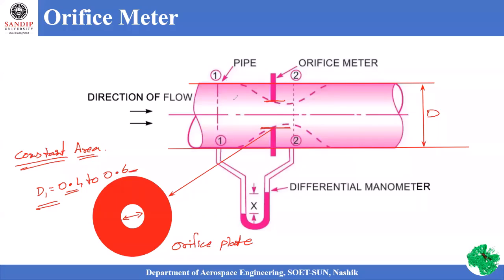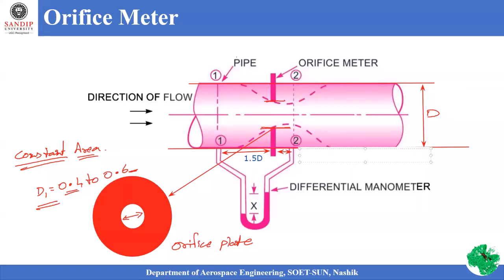The orifice plate is placed inside the meter construction and connected with a differential manometer. The manometer location should be at 1.5 times D ahead of the orifice plate, and the other end of the manometer should be connected at a distance of 0.5 times D behind the orifice plate.